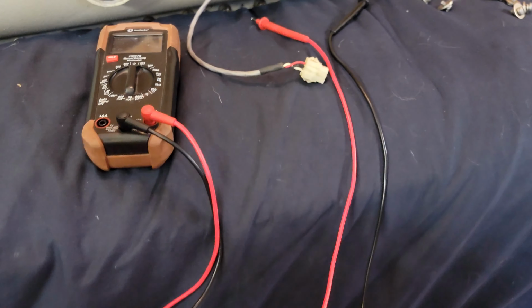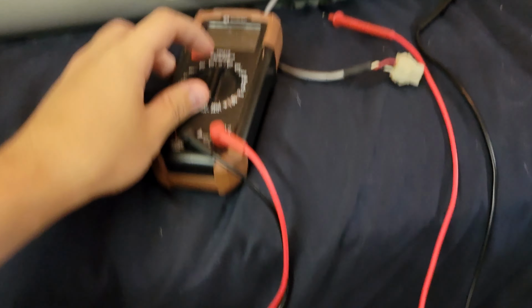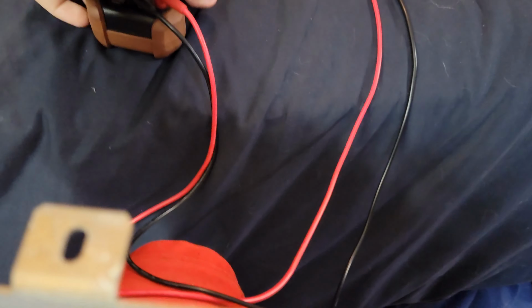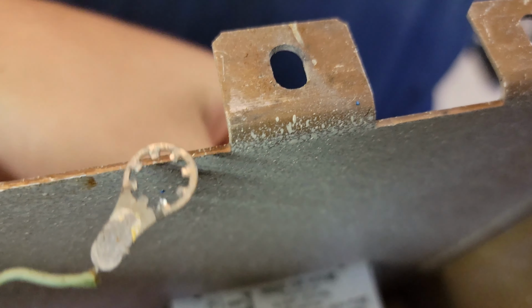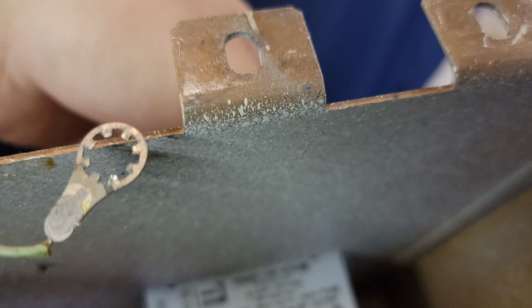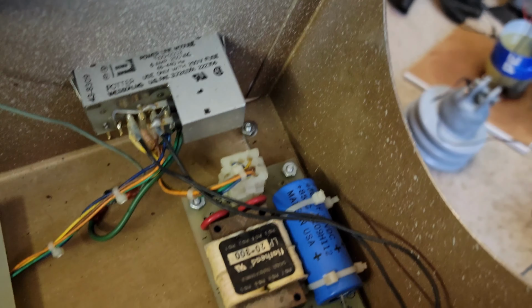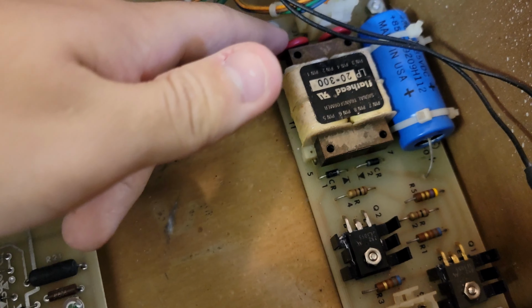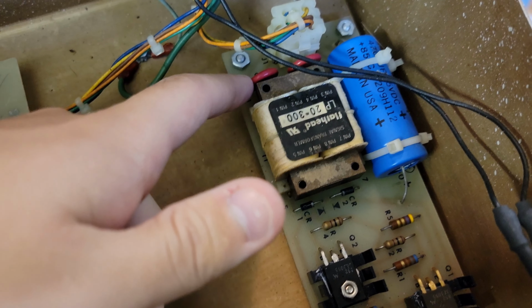So what I'm doing is putting this on resistance, going between ground and live, or ground and neutral, letting it sit for a bit, then switching to voltage. You can see there's actually voltage being held between ground and live, and ground and neutral. Maybe it's these.